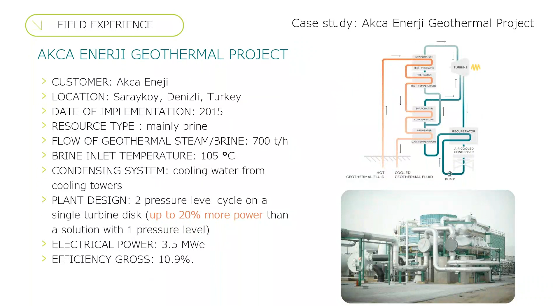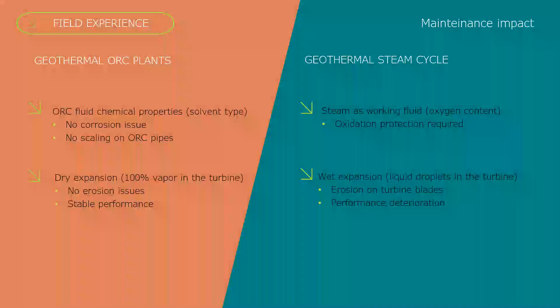Before diving into the specifics of maintenance in the ORC, I'll recall a couple of key differences that distinguish binary ORC plants from steam cycles. The first difference relates to the chemistry of the working fluid. In the steam cycle we have water, which means we have oxygen content in the plant, and this oxygen brings a series of risks related to corrosion and rust formation.